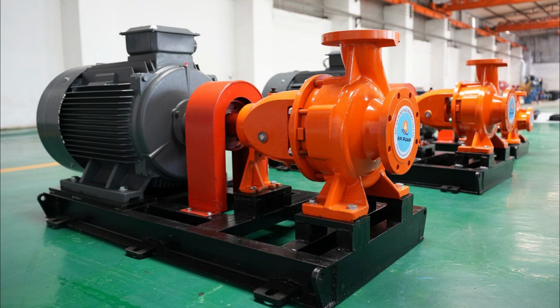So how do we make sure our pump's getting a nice steady drink of fluid? It's all about making sure the NPSH available, the actual pressure at the inlet, is higher than what the pump needs, called NPSH required. Got to have a tasty margin, keep the pump happy, make sure it's well fed.